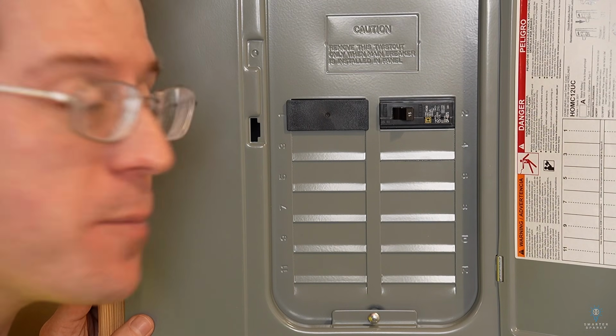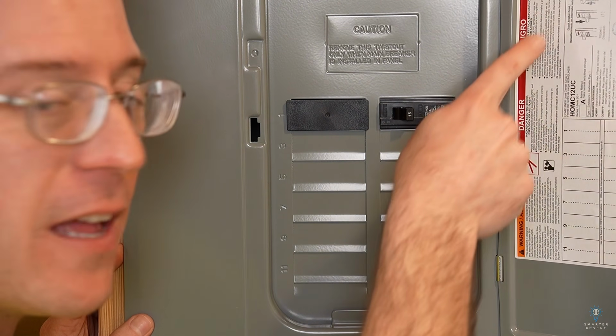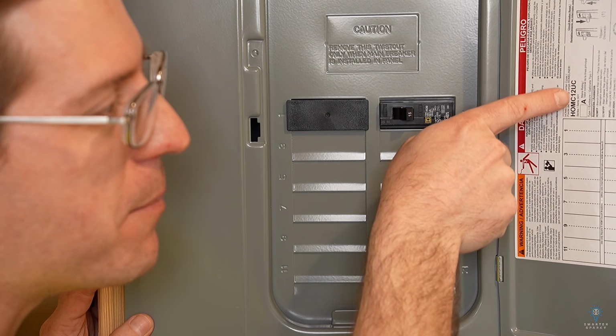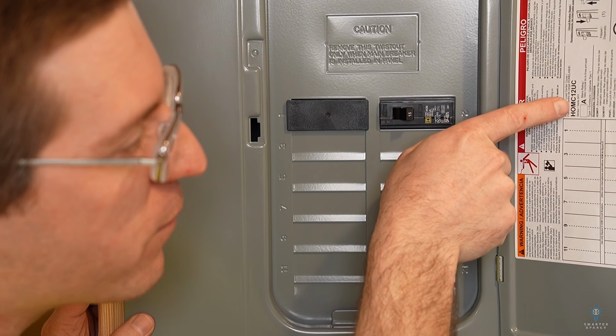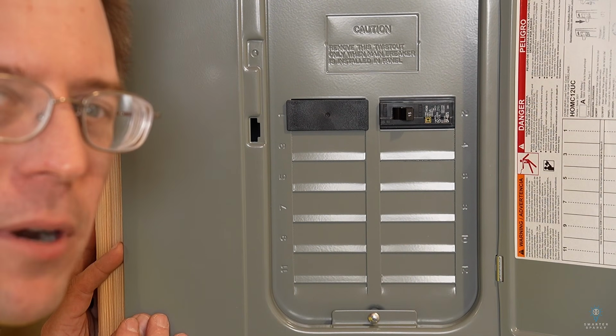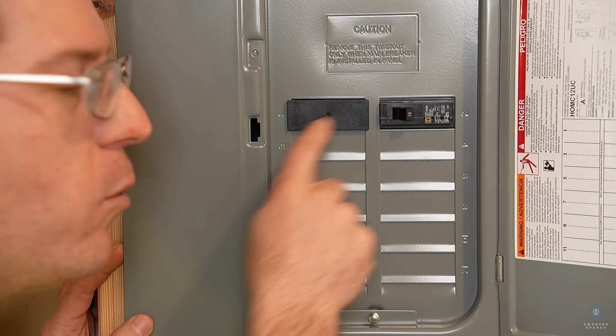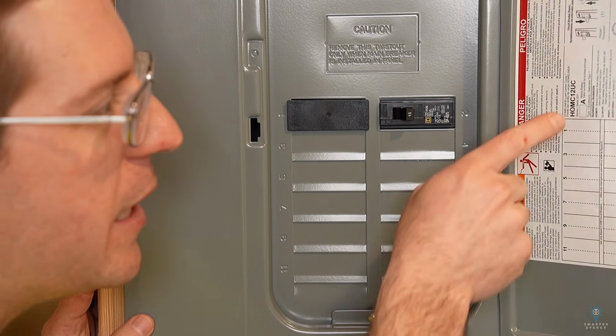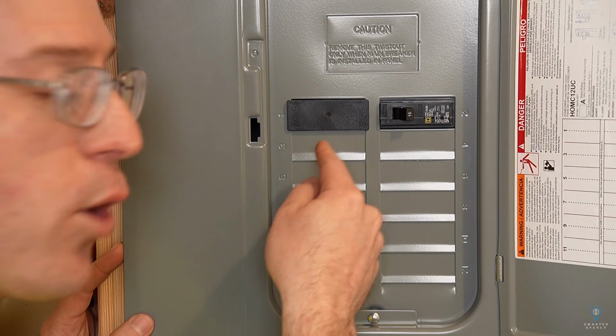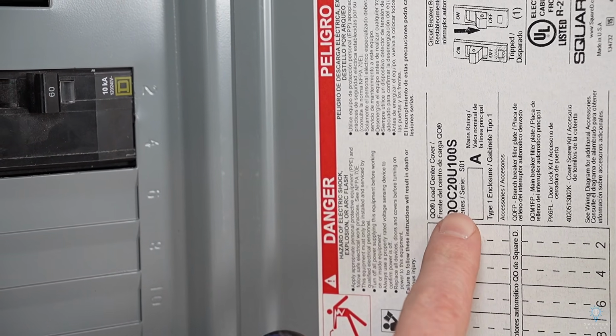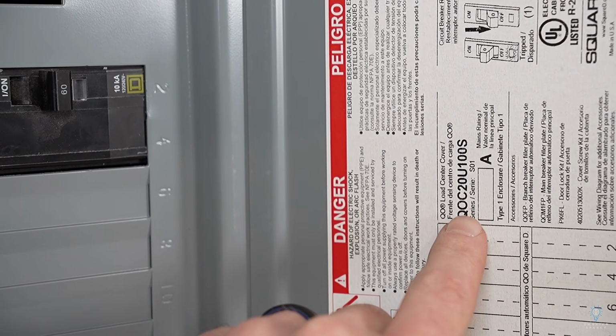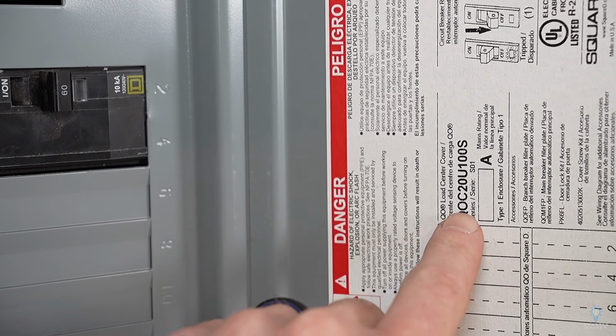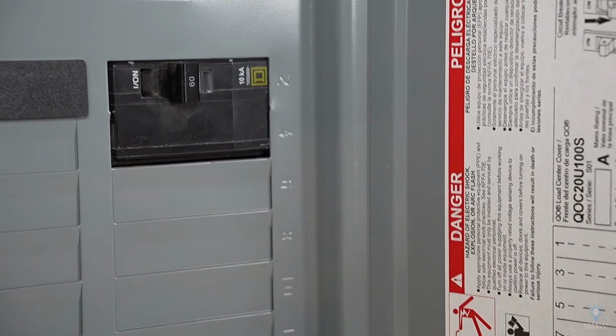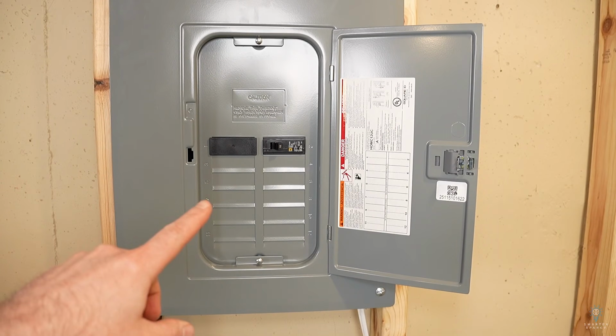Or for extra bonus points, take a picture of this sticker on the breaker panel cover. It actually gives the model number of the panel. And using the first couple letters of that model number, you can very quickly figure out exactly what type of breaker blanks you need. The HOM in this case stands for Homeline Series, whereas if we go over here to the main electrical panel, and we take a look at the cover on the main electrical panel, notice how it says QOC. This is a QO style panel. So these are QO breakers, and in our sub panel, these are Homeline breakers.